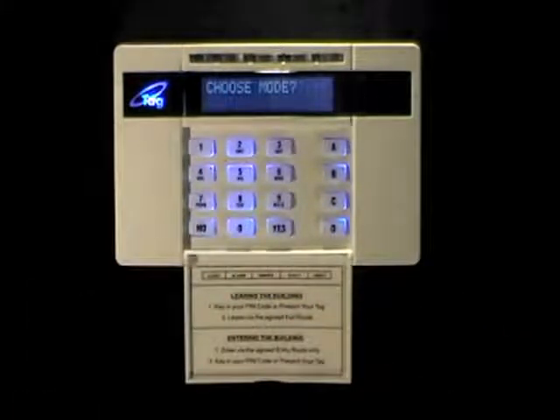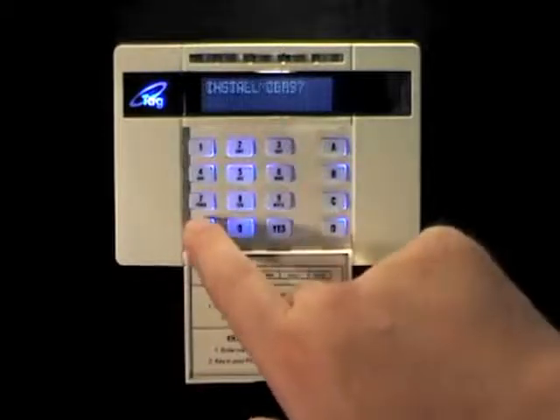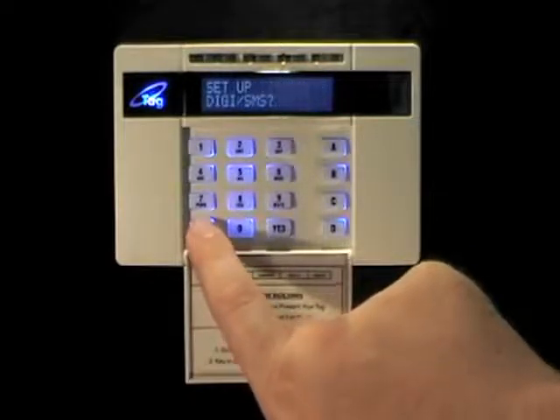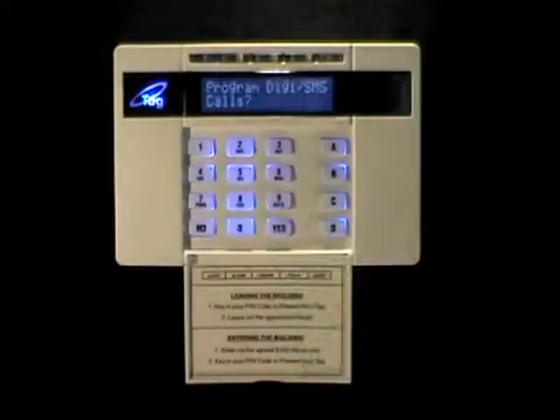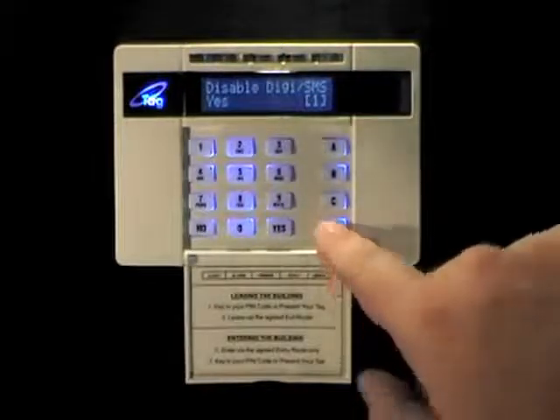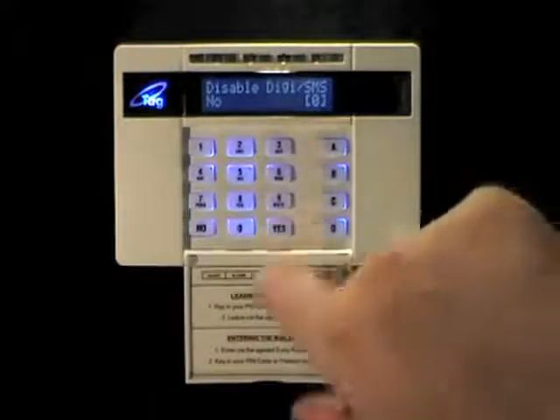Now press the no key to scroll through to the menu: Set up Digi SMS, and press yes. This menu — Program Digi SMS Calls — press yes. The first option you'll see is Disable Digi SMS, and the option is set to yes. This is a global switch to turn off all ARC and text messaging services on the panel. By default it's set to yes. Change it to no to enable communications, and press yes to continue.